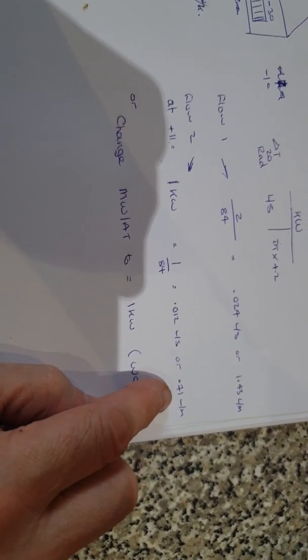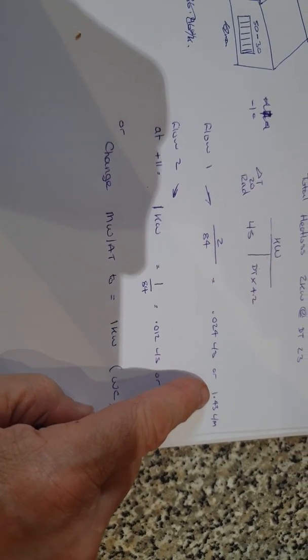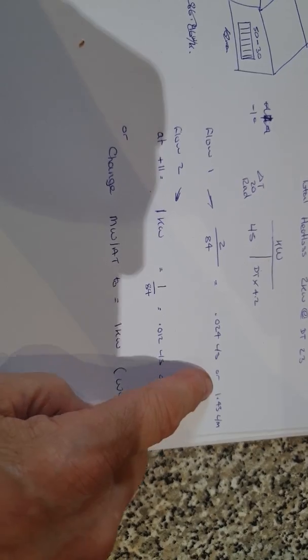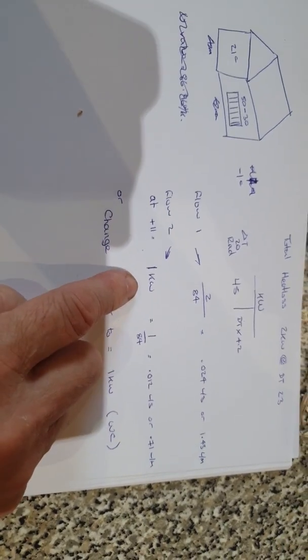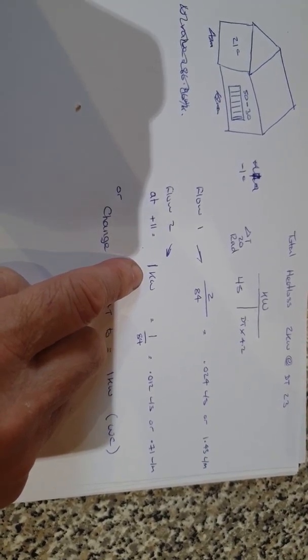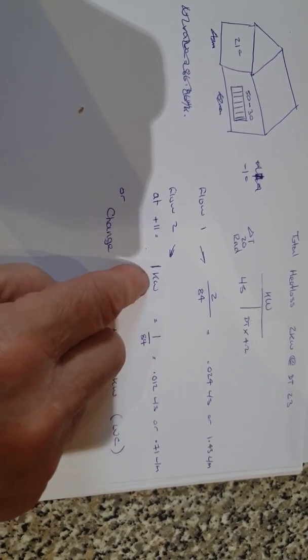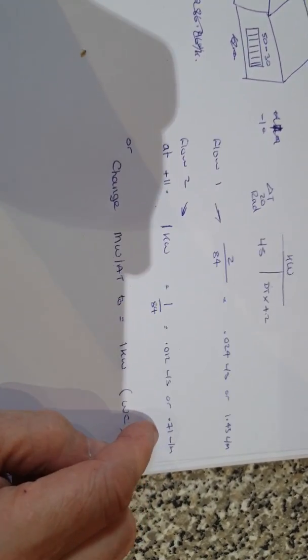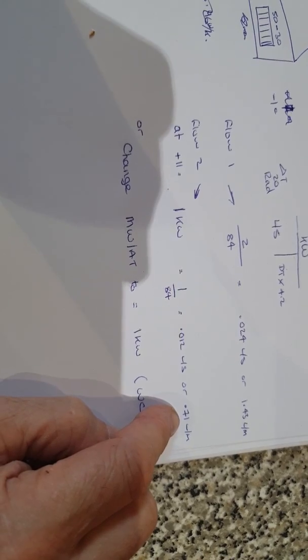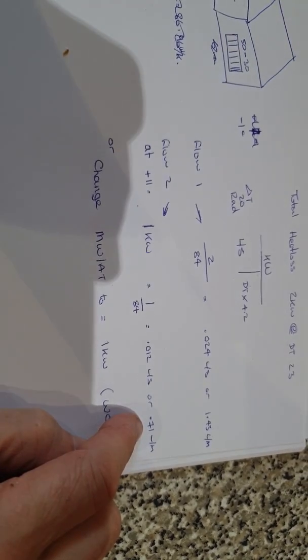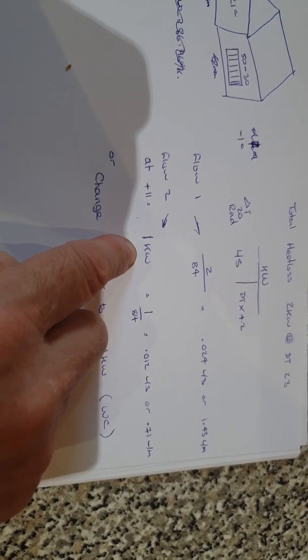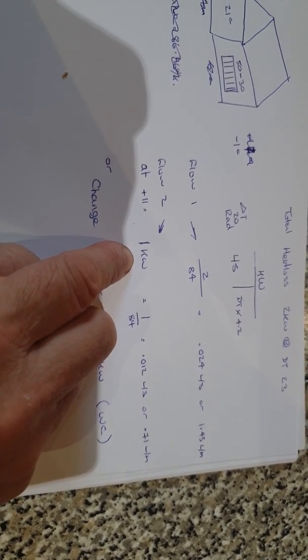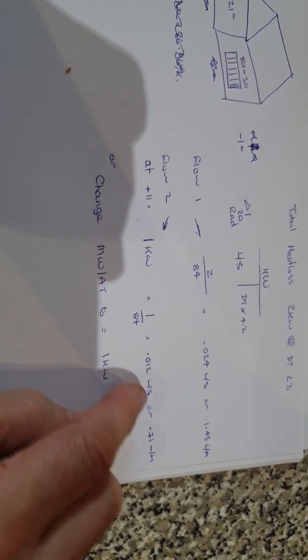We could actually balance for delta T 10, and what we'd actually be measuring then, if you go back to the mass flow rate, is that would prove that we had the same flow rate for the delta T 20 target. Or if we actually adjusted the flow to give us the one kilowatt to maintain 21, we would actually be measuring at 50 flow.